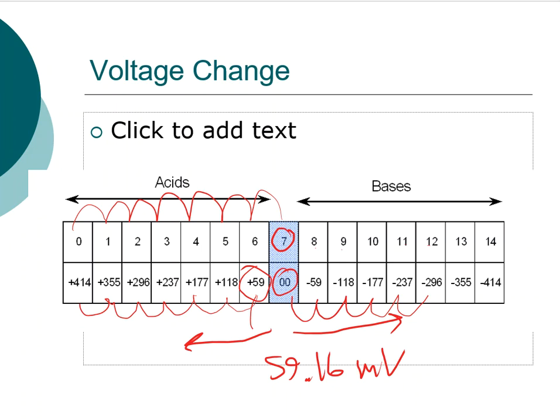So in the next video, we're going to talk more about the voltage now that we've made it to that point, and we're going to talk about how we can ensure that this meter is calibrated the proper way, because it will go wonky. And as a user, we have to calibrate these things very, very often. So how does that actually do its job? Well, you can kind of expect now that it does its job by looking at millivoltage. For instance, if I have a solution that has a pH of 4, I should be generating a millivolt reading of 177. Is it? Think of it like a calibration weight. If I have a calibration weight of 20 and I put it on the balance, is it really 20? The same thing is going to happen here with a pH meter. If I have a buffer 4 and I put that probe into that buffer, is it generating 177 millivolts? Because by definition, that is what should be getting created. And that's what we'll talk about in a little more detail in the upcoming video.